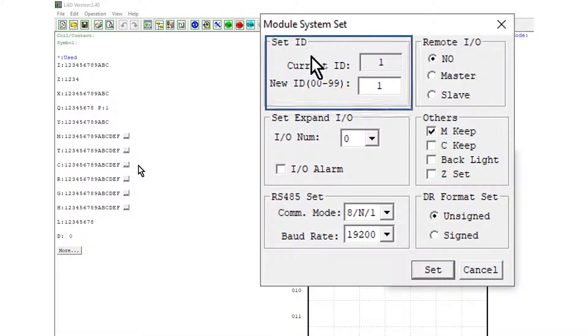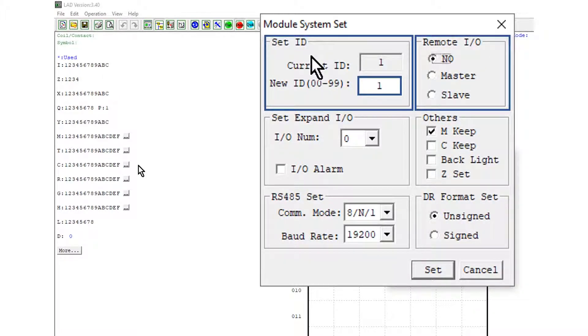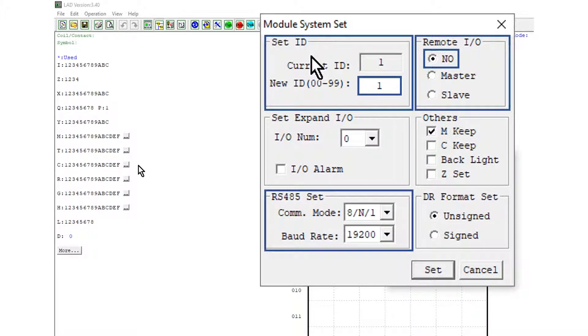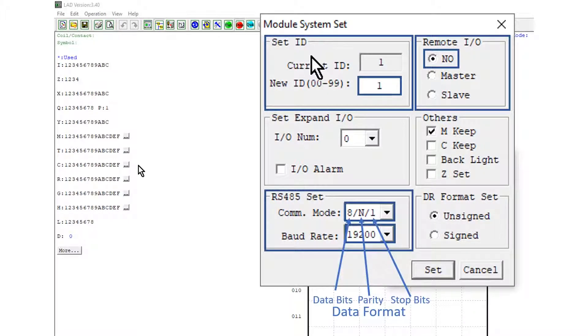From the Operation menu, select Module System Set. Set ID is the Modbus slave station number — one is selected in this example. In the Remote I/O window, select No. In the RS-485 window, select the baud rate; 19.2k is used in this example. Set the data format, then click Set to write the configuration to the SG-2.